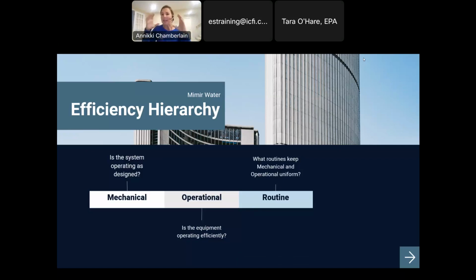So then finally, what I would consider the bulk is water management. Okay, now we've got a good water management system in place. Now we can start looking at paybacks. What's that upgrade that I can do? I'm really going to get a return on investment. So for a cooling tower, you might think, oh, let's put in a water softener and we're going to be more efficient because we take all the minerals out. But if you're constantly having mechanical failures, your set point is way too high or way too low, you're never going to achieve that ROI. So always trust the efficiency hierarchy.